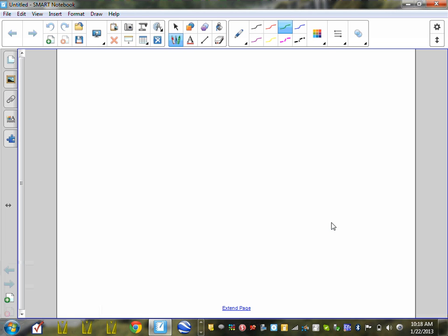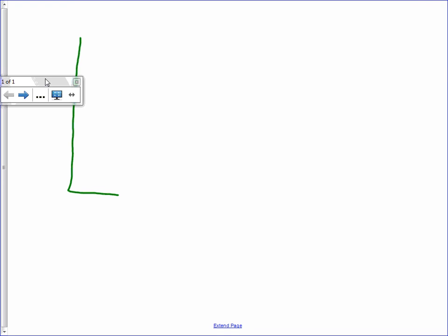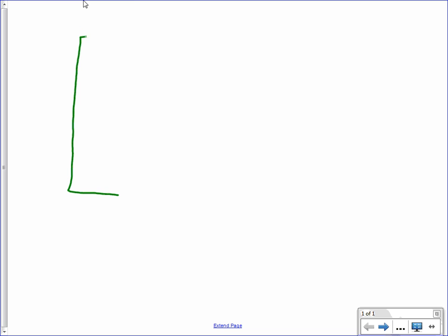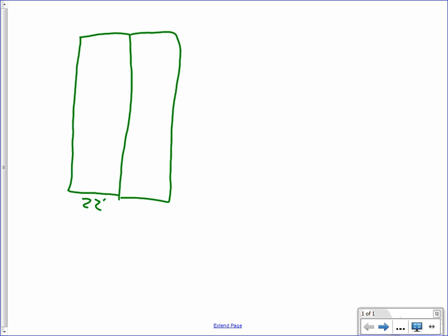Next up. Okay, in general, a switch gear section. I'm just giving you more room to draw. Again, we talked about switch gear being kind of thin and deep. A 3,000 amp breaker will fit in a 22 inch wide section.